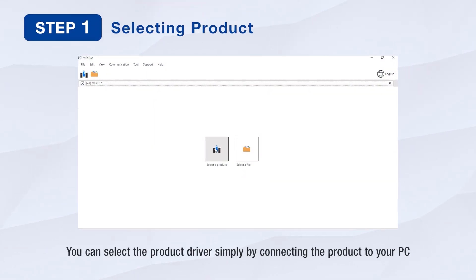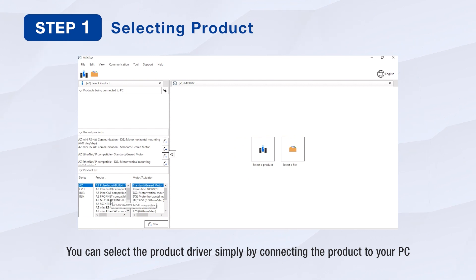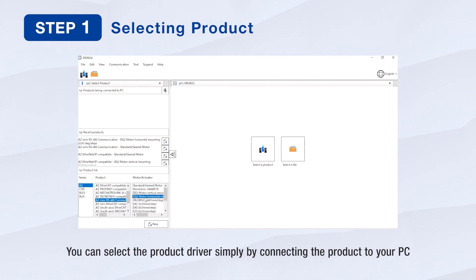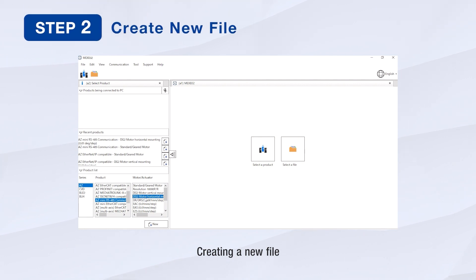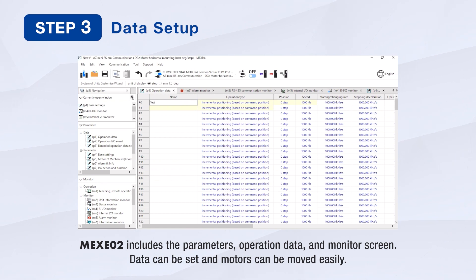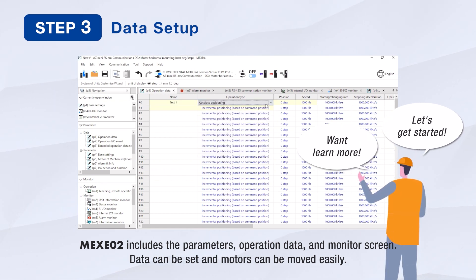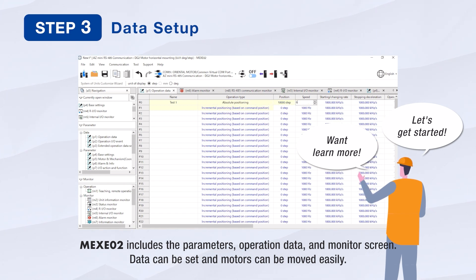Let us demonstrate an actual operation of the MEXE-02 support software. Simply connect the motor driver to your PC using the standard USB cable. From there, select the driver type. Create a new file. The MEXE-02 support software includes the parameters, operation data, and monitor screen. Data can now be set in the software and the motor can now start to move easily when commanded.